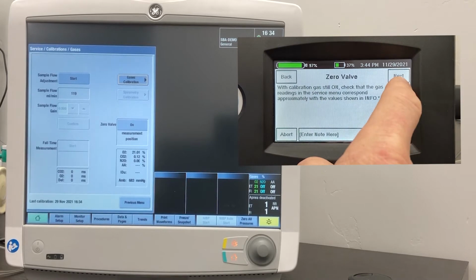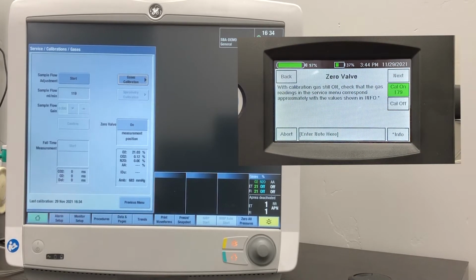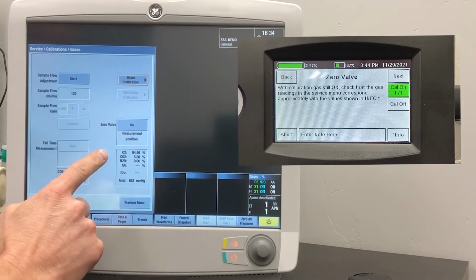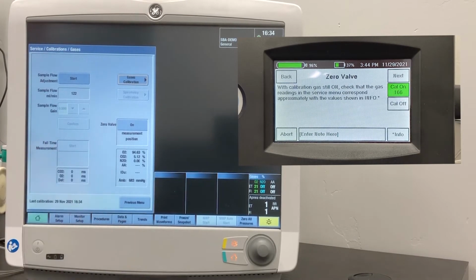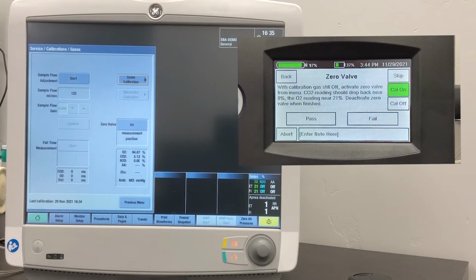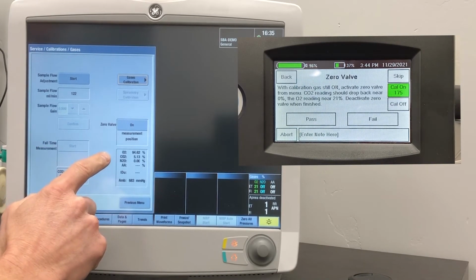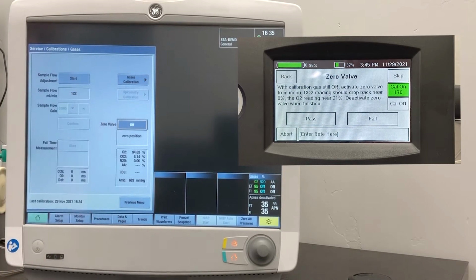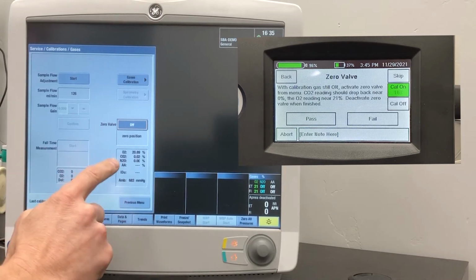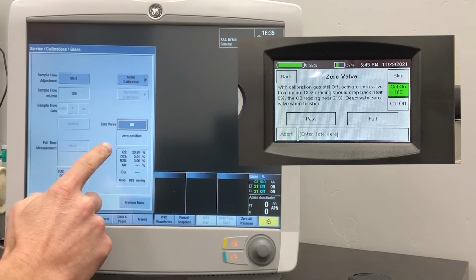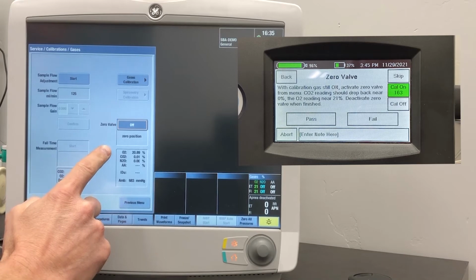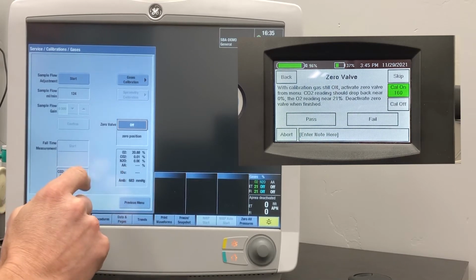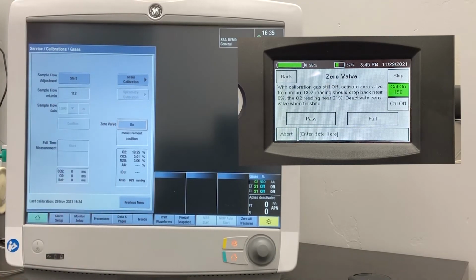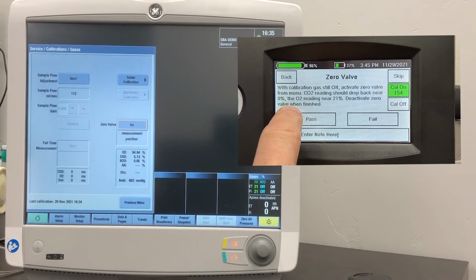Now we turn calibration gas on. We're going to test the zero valve. First we look over here and make sure that the readings correspond approximately to the gas. I'm going to hit next. Once they read approximately what the gas concentration is, we're going to test the valve by turning on the zero valve. We should see those values drop quickly to approximately room air oxygen, which is 20.9, and 0 CO2, which they did. Now we can turn that back on. So that is a passing result.